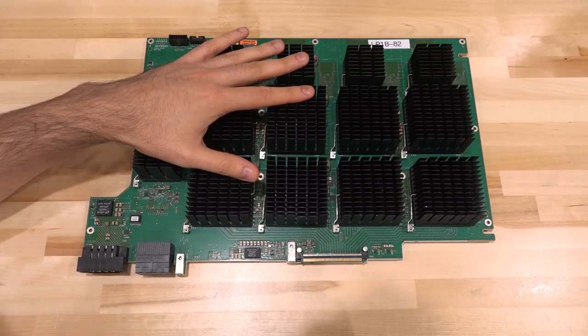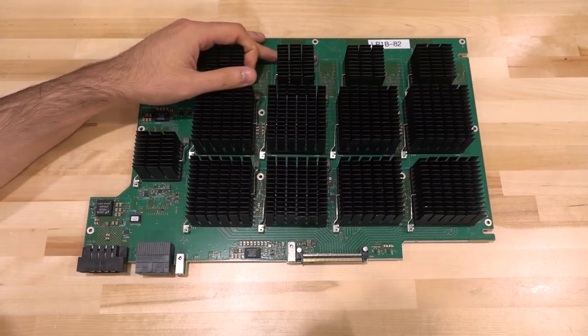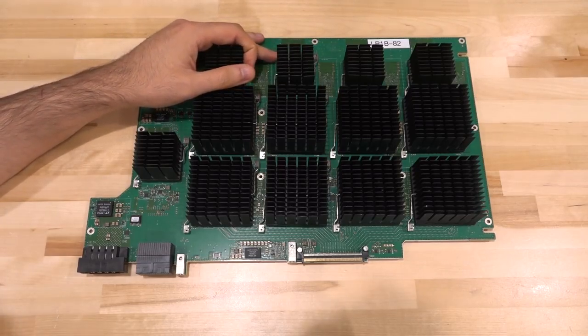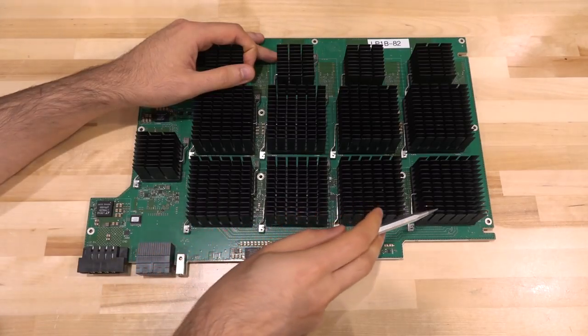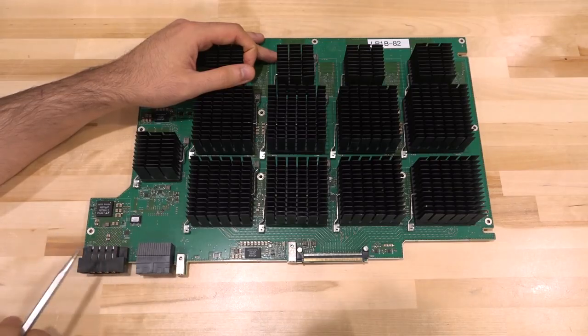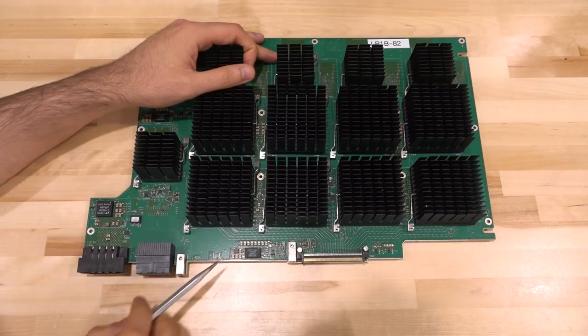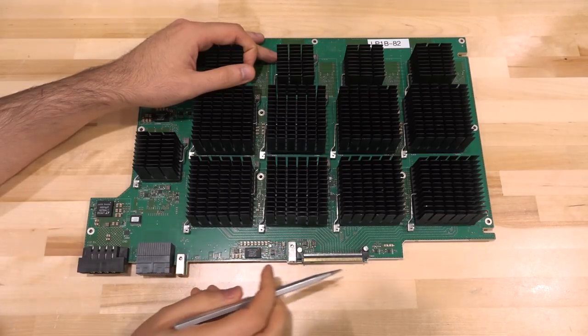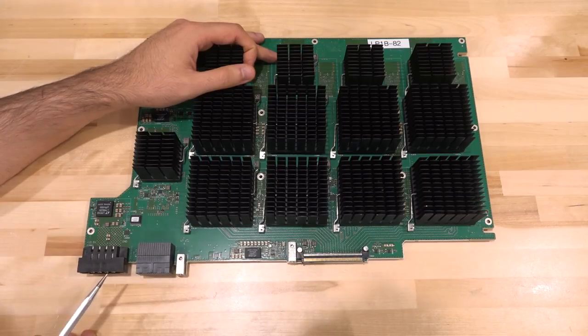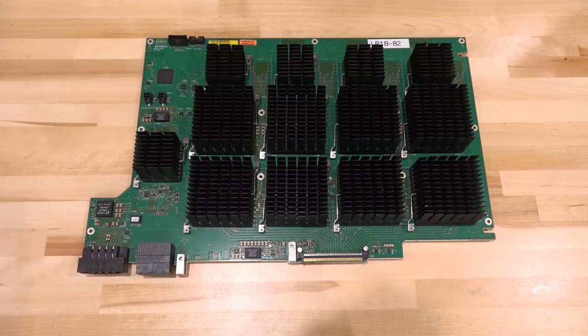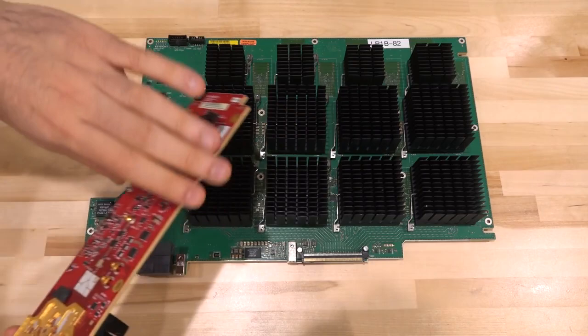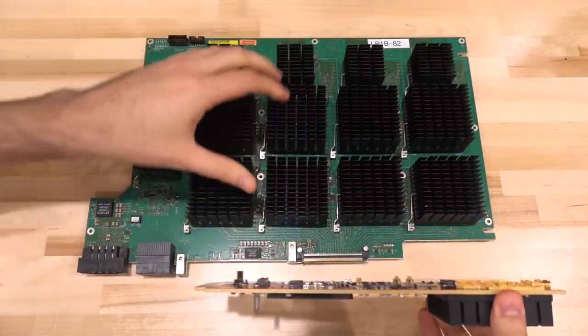So as we said, this needs to have 4 64 gigasample per second A-to-D converters in order to be able to get to 256 gig sampling, and with the 16 inputs coming from the front-end sampler I just showed you. So here's 1, 2, 3, 4 A-to-D converters, and each of these are 64 gig, 10 bits with 4 inputs. You can see some of the traces with the microstrip or strip lines that are going into it. So there's a front-end high-speed connector and an alignment pin that allows you to interface with the front-end sampler. So all the analog signals have to travel as little as possible, and they've come up with this solution with this connector. There is a front-end sample there, module there.